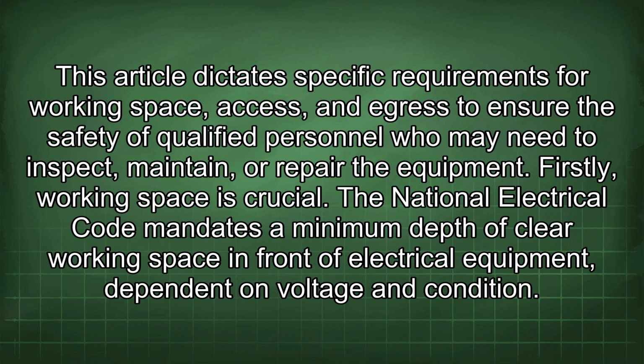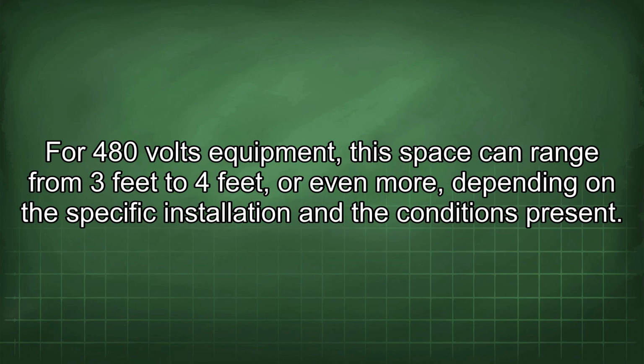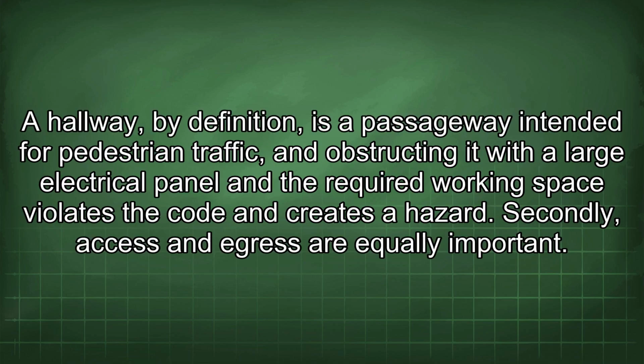Firstly, working space is crucial. The National Electrical Code mandates a minimum depth of clear working space in front of electrical equipment, dependent on voltage and condition. For 480 volts equipment, this space can range from 3 feet to 4 feet, or even more, depending on the specific installation and the conditions present. A hallway, by definition, is a passageway intended for pedestrian traffic, and obstructing it with a large electrical panel and the required working space violates the code and creates a hazard.